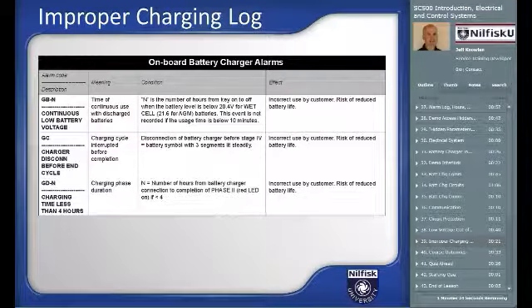The function board monitors the battery charging process and will log conditions where the batteries are being abused. These logged conditions will not show up as an alarm code to the operator, but they will be recorded in the alarm log for the technician to retrieve. If reduced battery life occurs, the log records may provide some evidence of why the batteries failed.